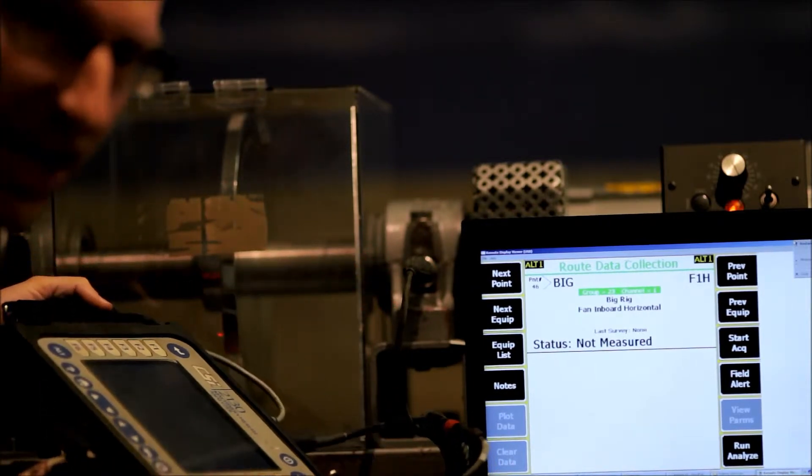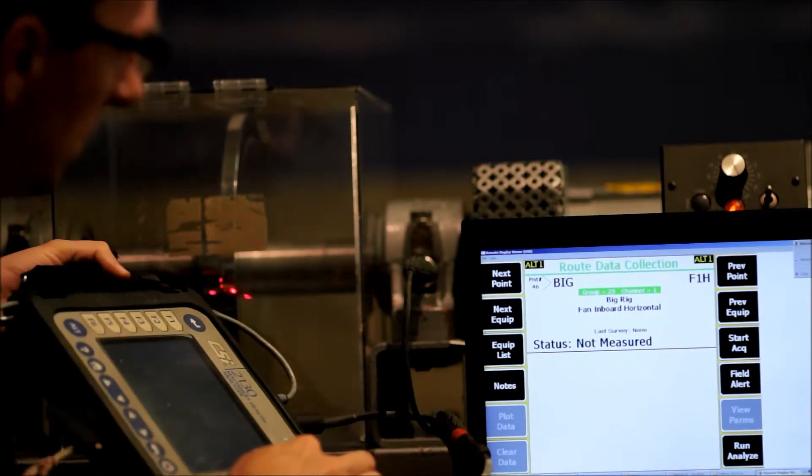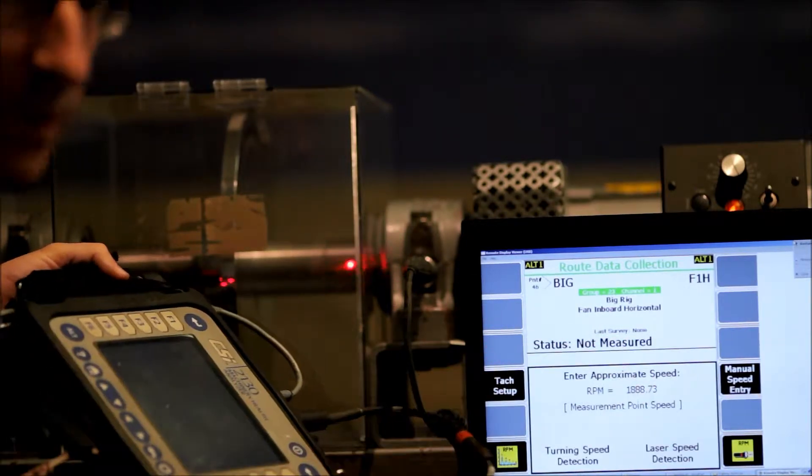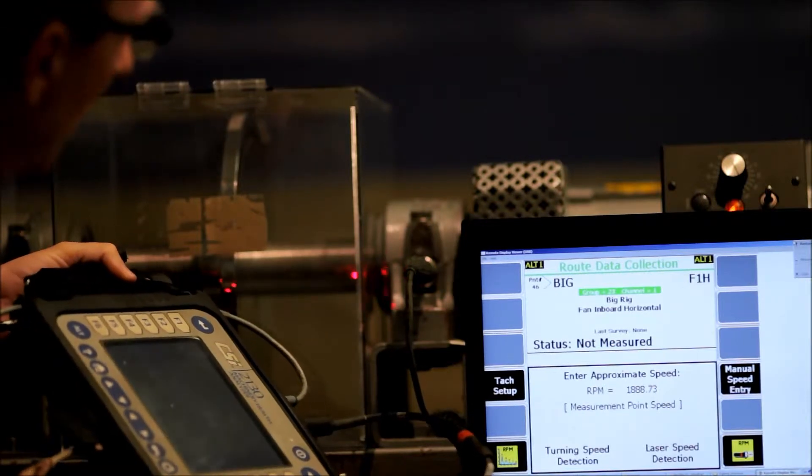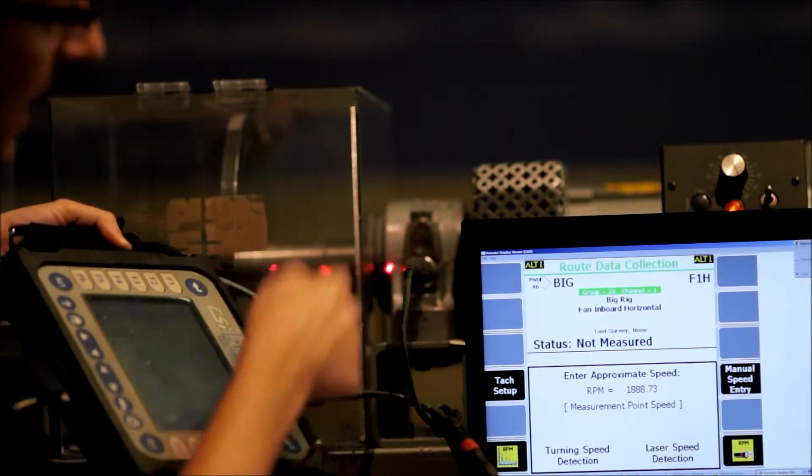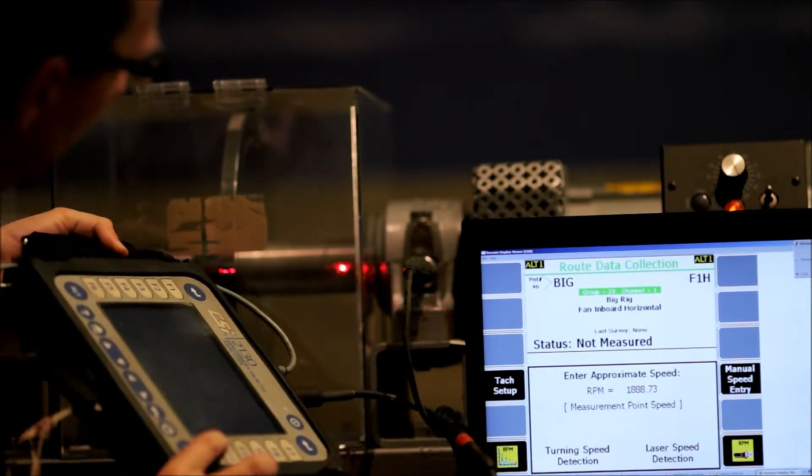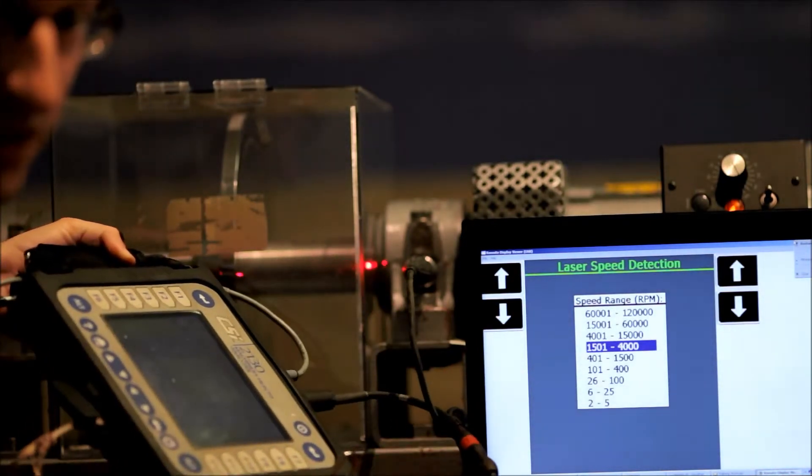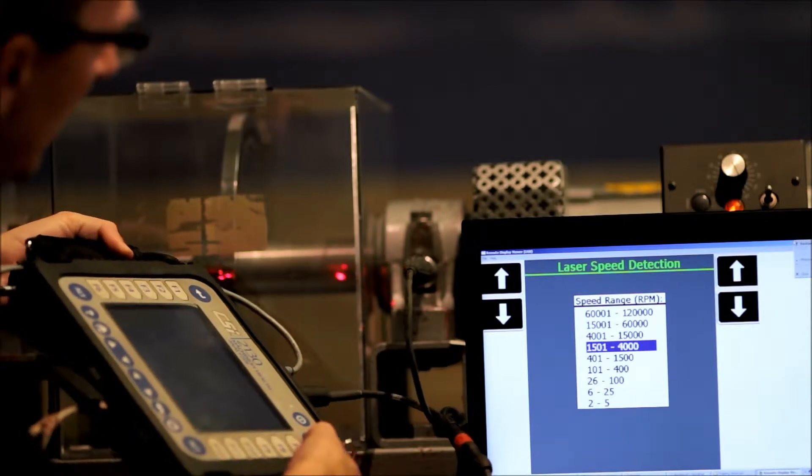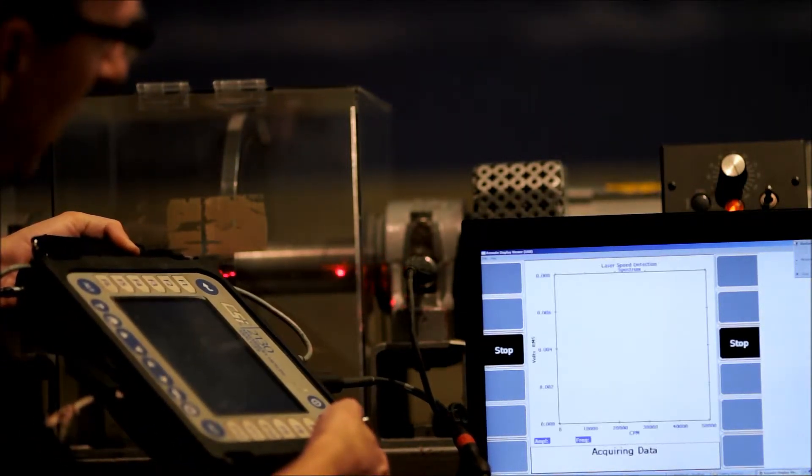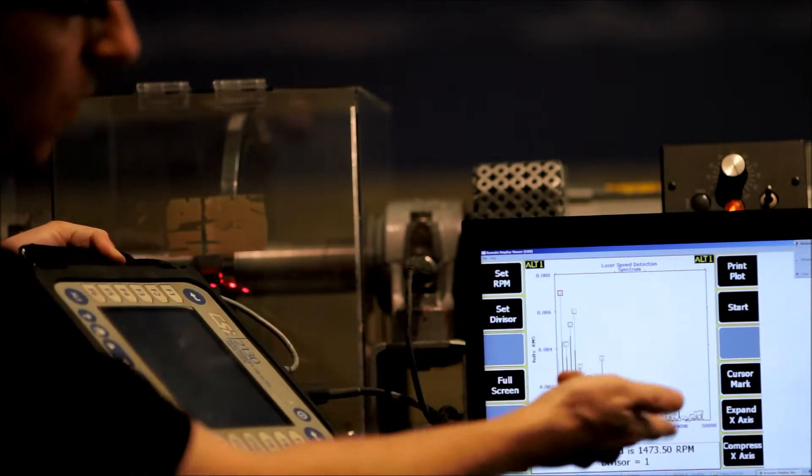So the first thing to do, I'm going to hit enter to start the data acquisition. It's prompting me for a speed of this shaft. So what I have to do is point the laser at the shaft and hit laser speed detection. It's going to give an approximate speed range. I hit enter to start data recording. It's going to spend a few seconds acquiring data from the laser beam, and it's acquired the correct speed.